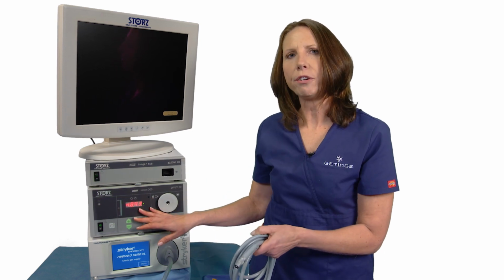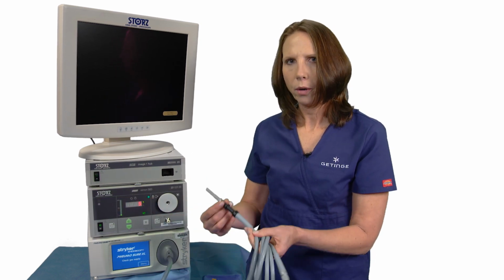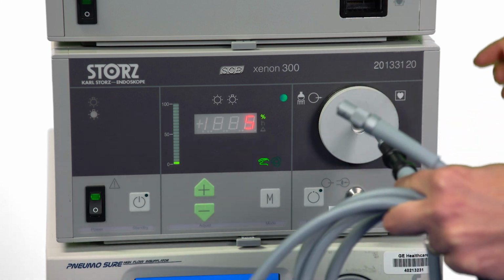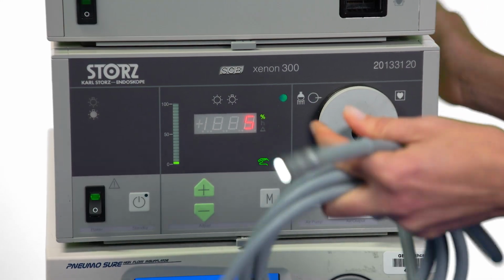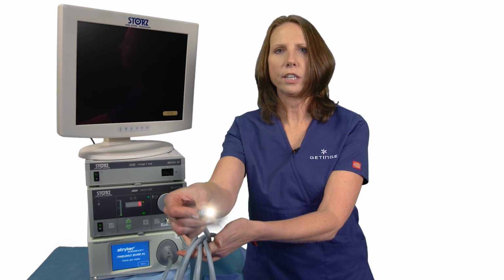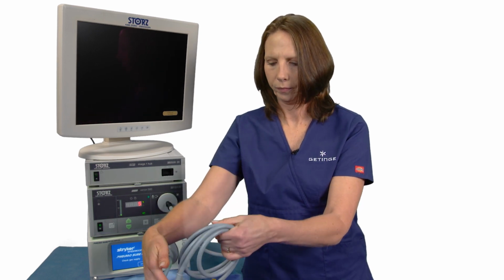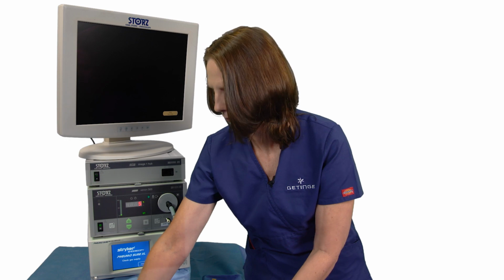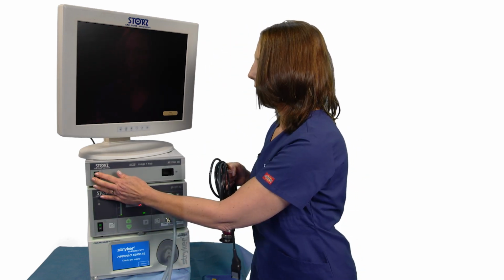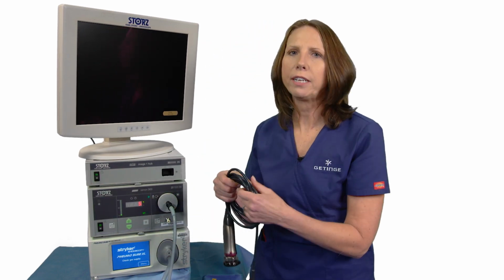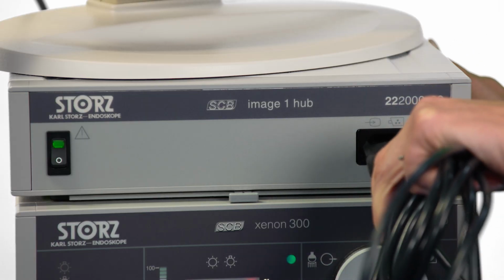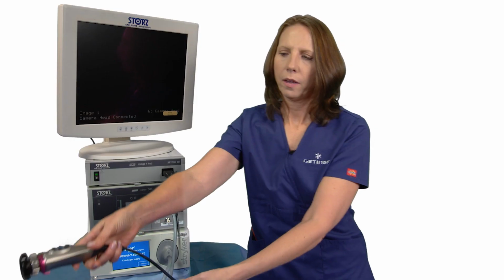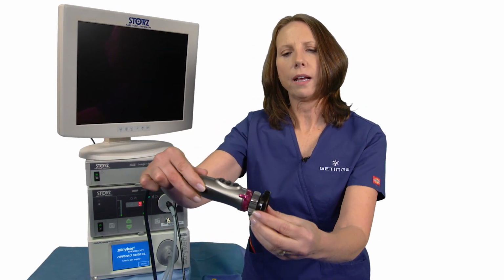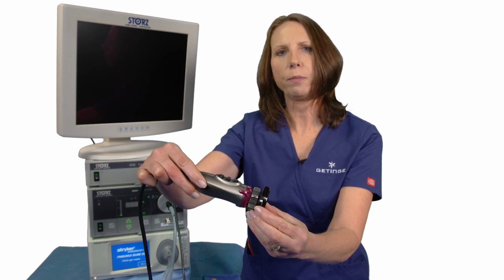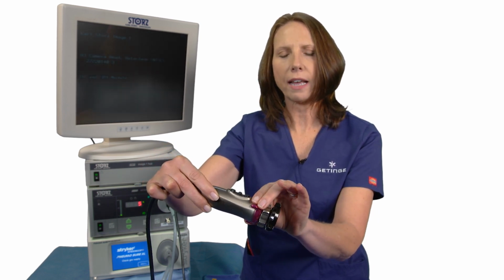The light box generates light for the endoscope. One end attaches to the light box, and the other end attaches to the endoscope. The camera box is what generates the image. The camera head attaches to the camera box. The camera head has a coupling device here for the endoscope, also has a focusing and a zoom.